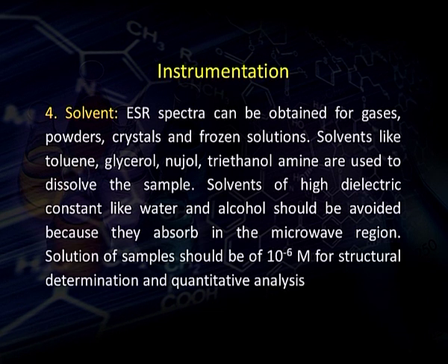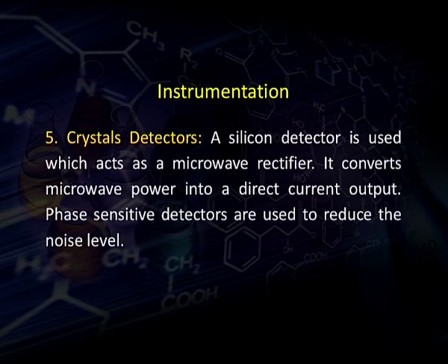If we use solvents of high dielectric constant like water, what will happen? Along with the sample, the solvent will also absorb the microwave radiation, so we won't get the proper result. Solutions of the sample should be of 10 to the power minus 6 molar for structural determination and quantitative analysis. That is, we should use very dilute solutions. The next component is the crystal detector. A silicon crystal detector is used, which acts as a microwave rectifier.